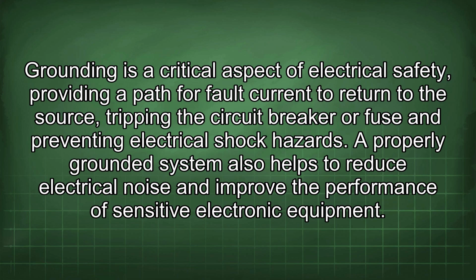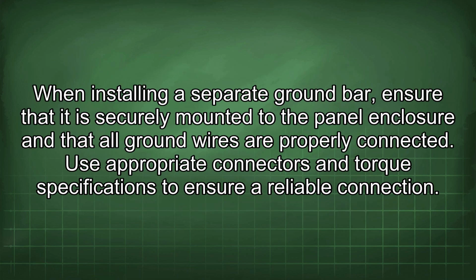Grounding is a critical aspect of electrical safety, providing a path for fault current to return to the source, tripping the circuit breaker or fuse and preventing electrical shock hazards. A properly grounded system also helps to reduce electrical noise and improve the performance of sensitive electronic equipment. When installing a separate ground bar, ensure that it is securely mounted to the panel enclosure and that all ground wires are properly connected. Use appropriate connectors and torque specifications to ensure a reliable connection.